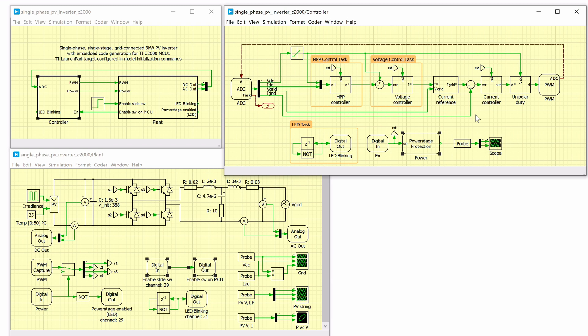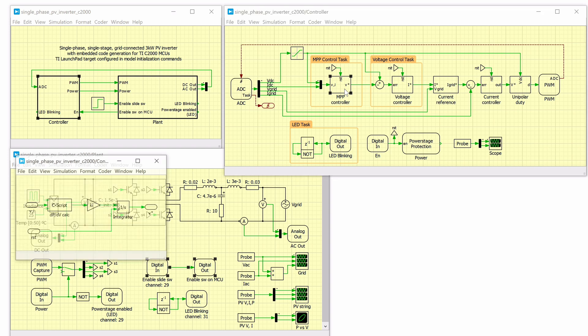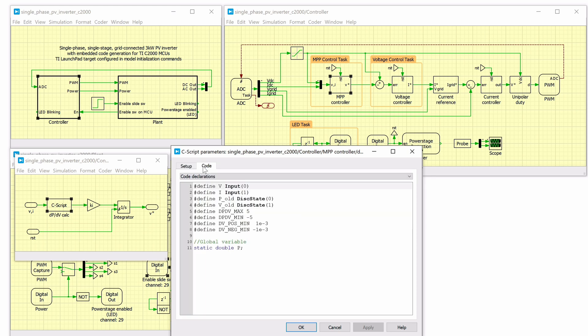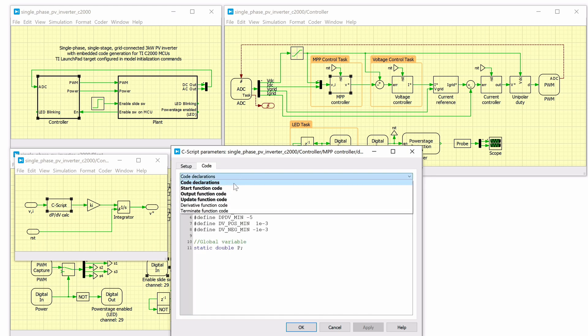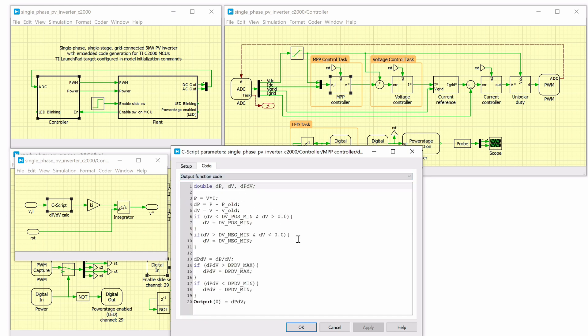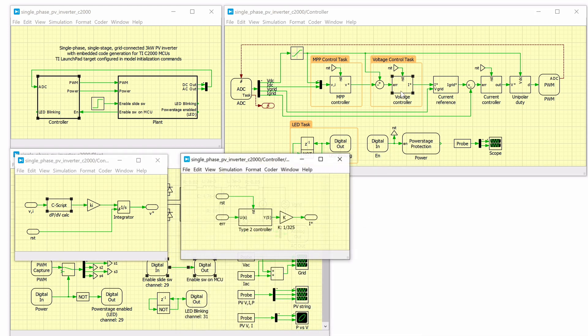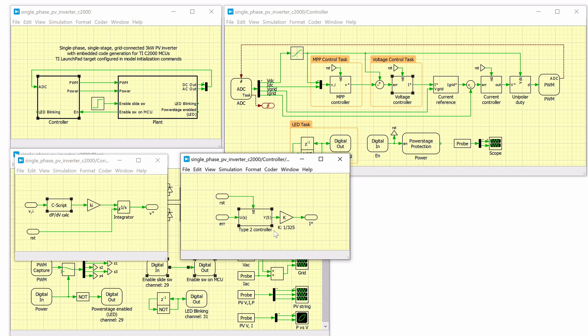The controller subsystem has three control loops. The outer control loop is a MPP controller that ensures maximum power is extracted from the PV string for a given insolation level. To do this, it calculates the optimal PV terminal voltage using an MPP algorithm known as DP over DV or incremental conductance control implemented using a C script block. The voltage control loop based on a type 2 controller regulates the PV voltage to this optimal level by controlling the amount of current that is injected into the grid.